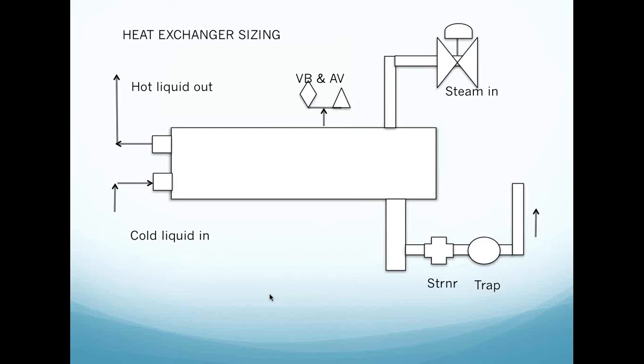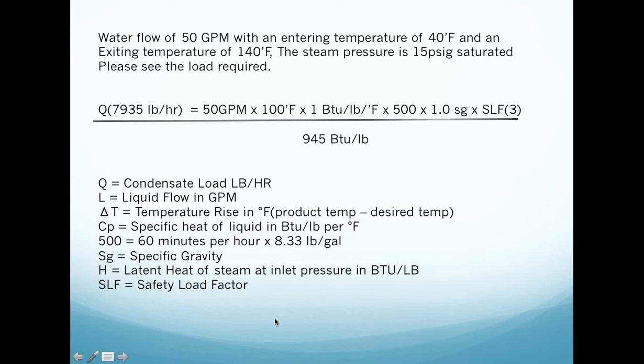And remember this, and I mentioned it before, if you have modulating inlet steam pressures, and you'll see on this simple drawing a steam control valve on the inlet side, but as it satisfies the temperature of that liquid on the outlet side, and we lose the steam pressure to help us push the condensate through this particular steam system, I am going to have a very difficult time getting that condensate wherever we have intended it to go. And boy, oh boy, have I had a lot of water hammer problems recently with heat exchangers. So please be careful. If you experience any of those, shoot me an email, give me a call, and we'll discuss that. I've got some sizing for heat exchangers, and Maureen's going to make this available so you'll be able to go back through it and take a peek at it.